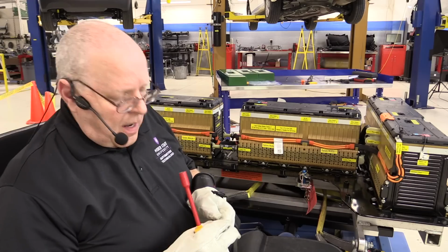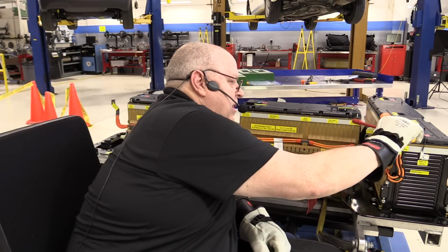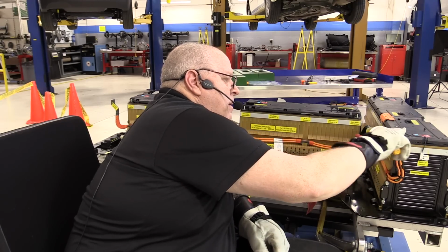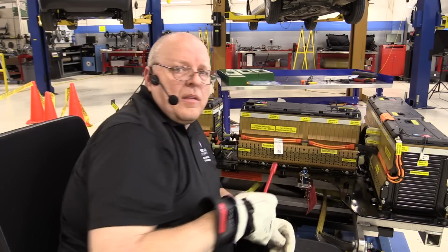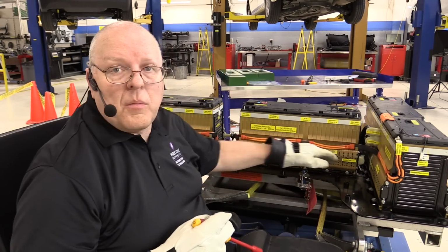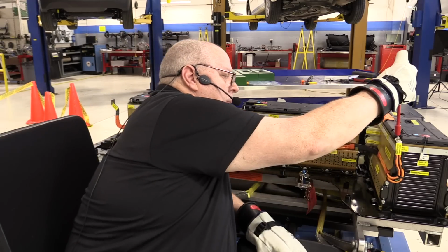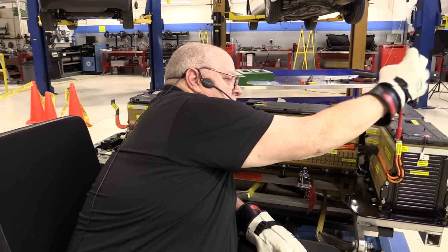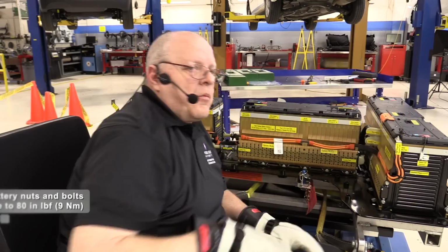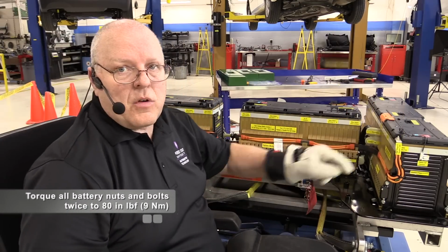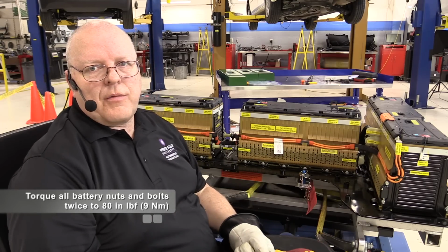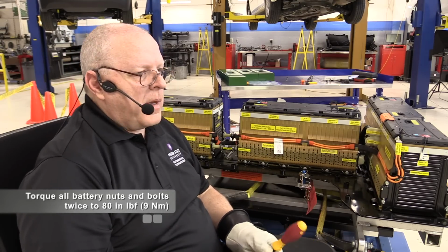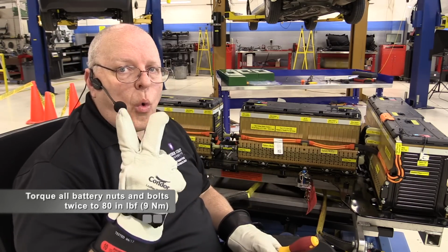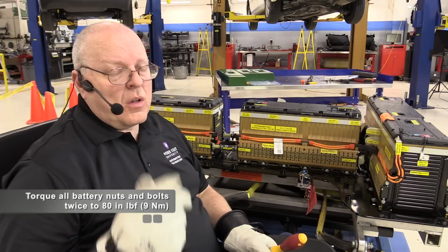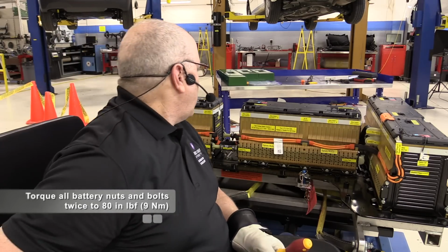The torque on these battery studs, or nuts on the studs, is the same 80 inch-pounds that we use to hold the battery retainers down. But this is such an important connection that the service information says they need to be clean and dry, no oil, grease, or antifreeze on them. And you check the torque twice because it's such a critical torque.